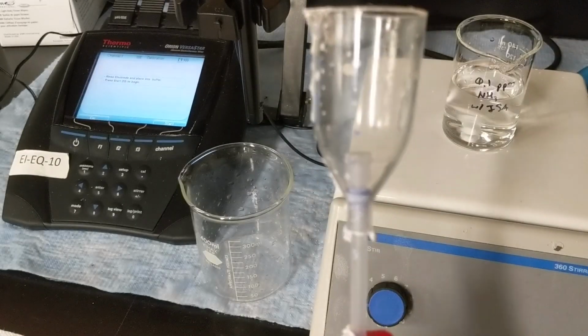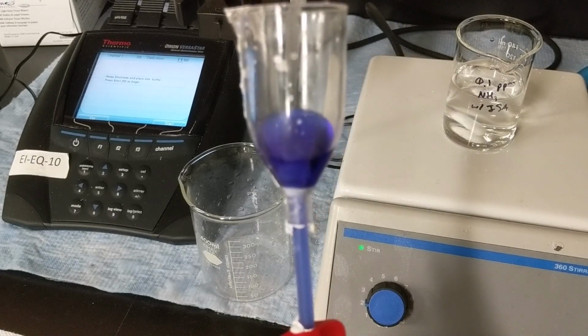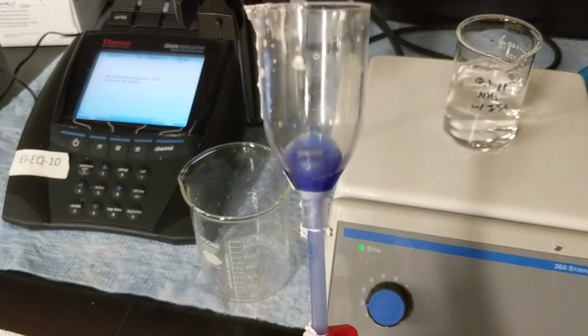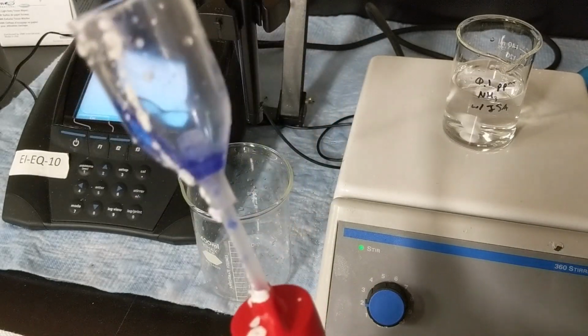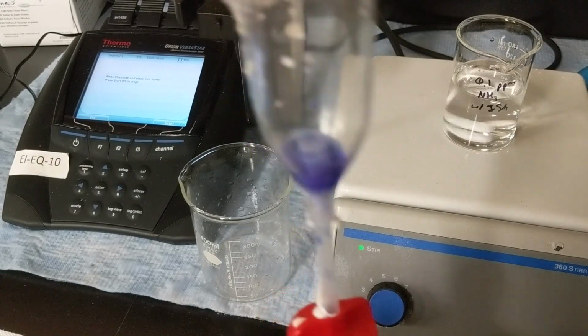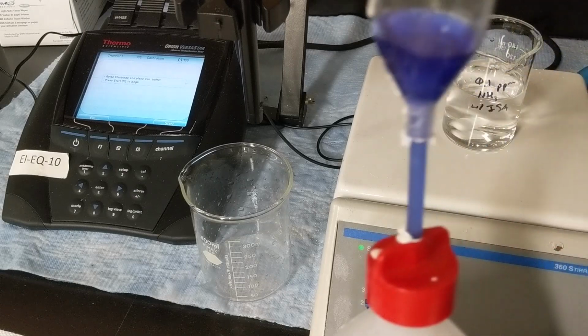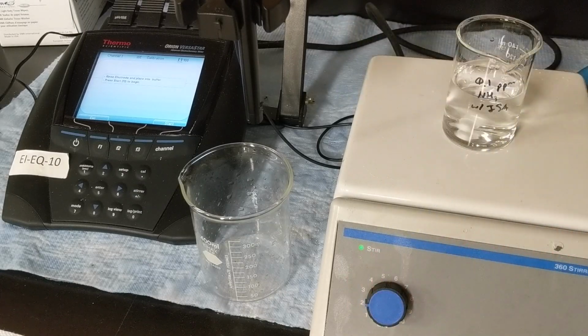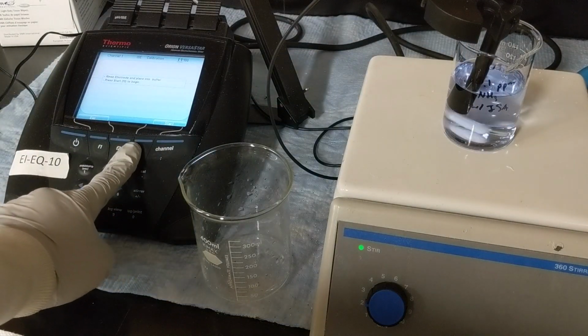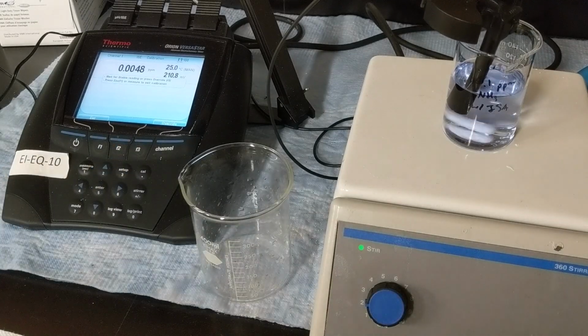It has this top on here where if you squeeze the bottle, some of the solution will come up, and then when you let it go, it will drain down to a specified volume. And so we have this set, or it should be set at 1.5 milliliters. I think it's actually, no, that should be about right. It's just a little weird to look at on the tilted camera. Okay, so again, squeeze that up and then let it drain back down to where it's supposed to be, and then we can just dump that into our calibration standard. And put the electrode in and hit the F3 button to start the calibration. Now these measurements are often very long, so I'm going to stop talking and fast forward the video until this stabilizes.